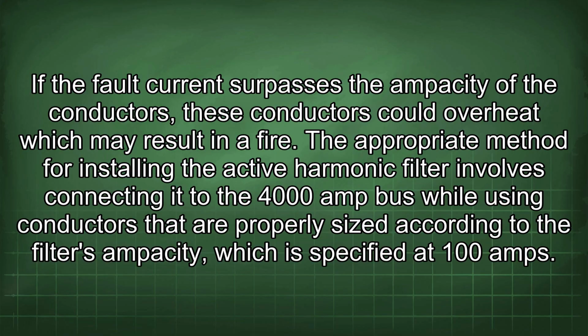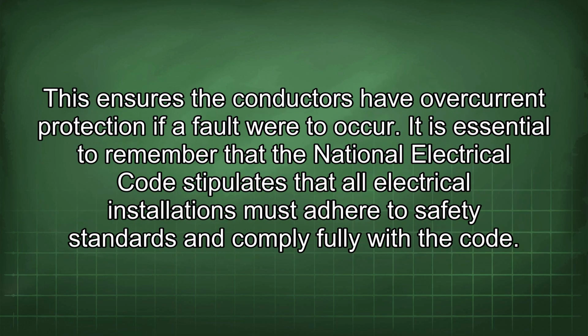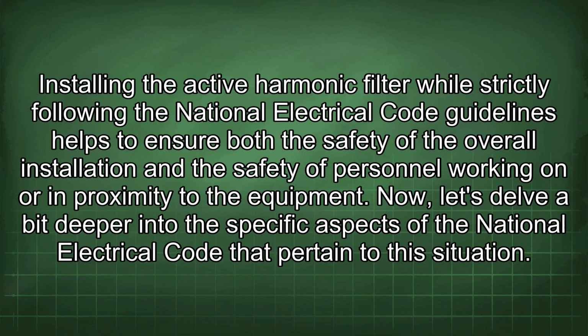a fire. The appropriate method for installing the active harmonic filter involves connecting it to the 4000 amp bus while using conductors that are properly sized according to the filter's ampacity, which is specified at 100 amps. This ensures the conductors have overcurrent protection if a fault were to occur. It is essential to remember that the National Electrical Code stipulates that all electrical installations must adhere to safety standards and comply fully with the code. Installing the active harmonic filter while strictly following the National Electrical Code guidelines helps to ensure both the safety of the overall installation and the safety of personnel working on or in proximity to the equipment.